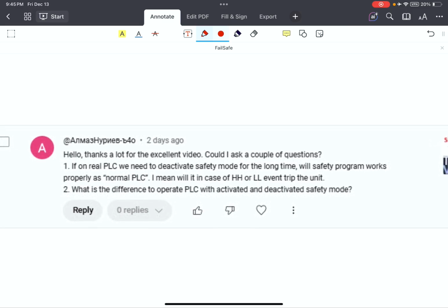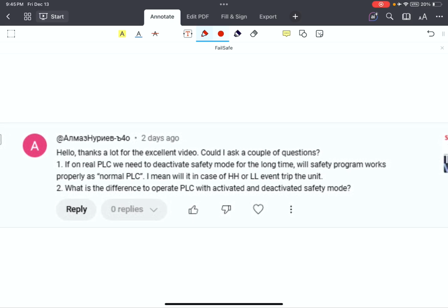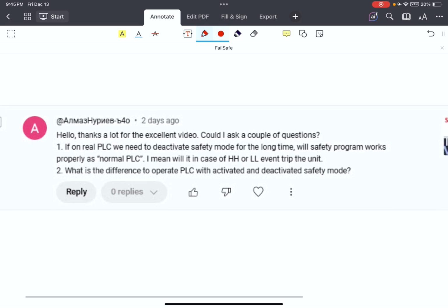these two questions. Could I ask a couple of questions? Yes. If on a real PLC we need to deactivate safety mode for a long time, will the safety program work properly as a normal PLC? I mean, will it, in case of an HH or LL event, trip the unit? Two, what's the difference to operate a PLC with activated and deactivated safety mode?